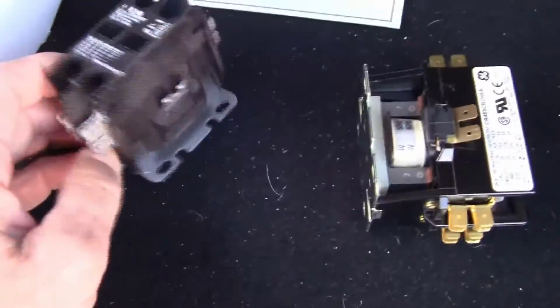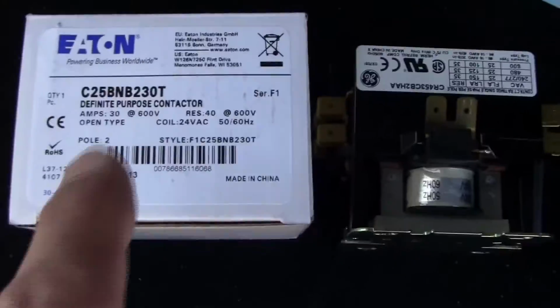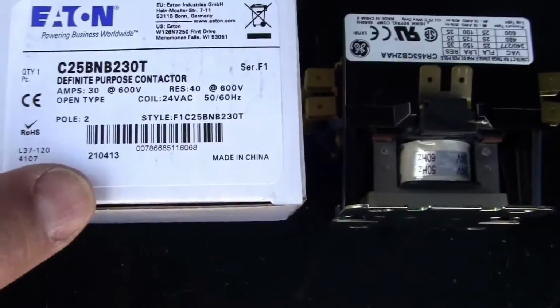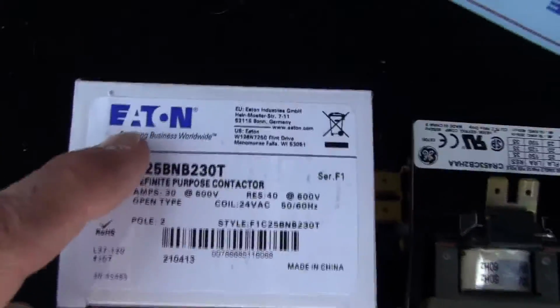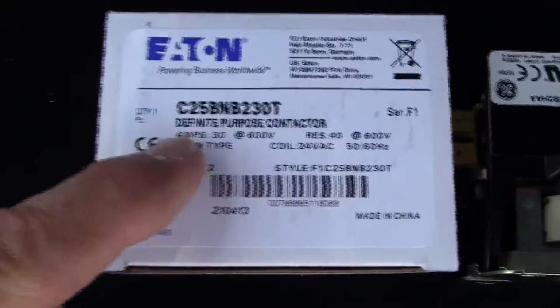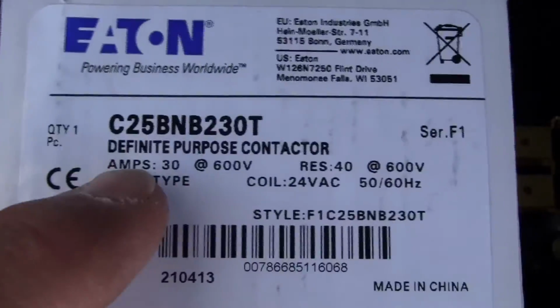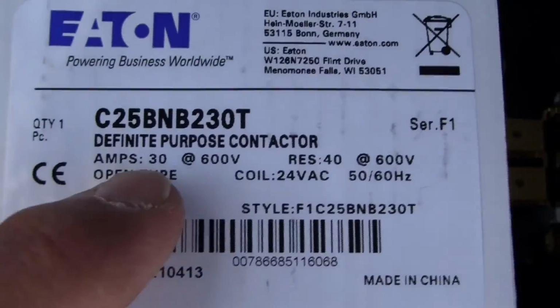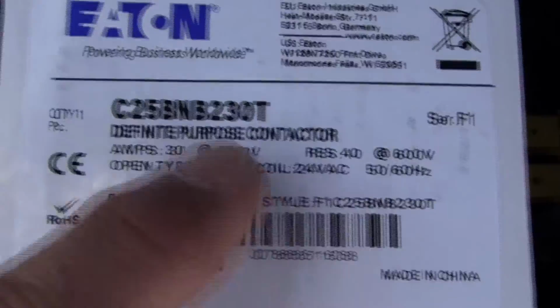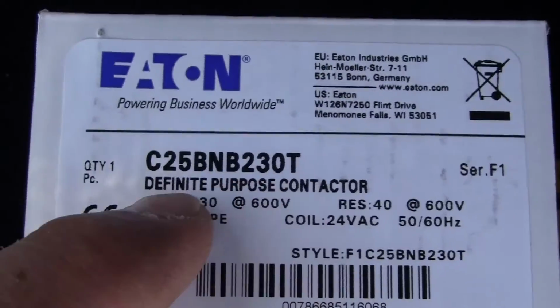Oh, another thing that I look at is the footprint. Put the 2 back to back, and I verify that the holes match up. So that way I don't have to drill more holes. So this is an actual drop-in replacement that's going to take care of our job. By the way, here's the model number of the brand new contactor. So it's an Eaton contactor, the definite purpose contactor, and it gives you the 30 amp rating, 24 volt coil, and there's the model number.